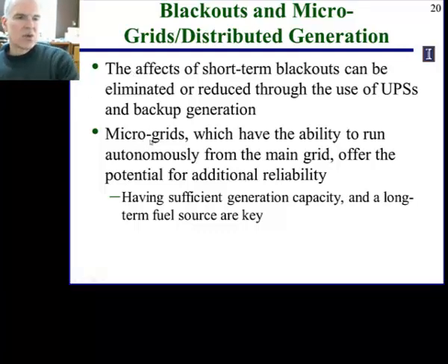Okay, a new trend that is being developed is what's called microgrids. A microgrid is setting up an interconnected electric power grid which has the ability to run autonomously from the main grid and offer the potential for additional reliability. So a microgrid is one where you take a number of smaller generators, set them up in such a way that they can run interconnected, and then have the necessary control systems in place so that if you lose the main electric grid, you can operate autonomously.